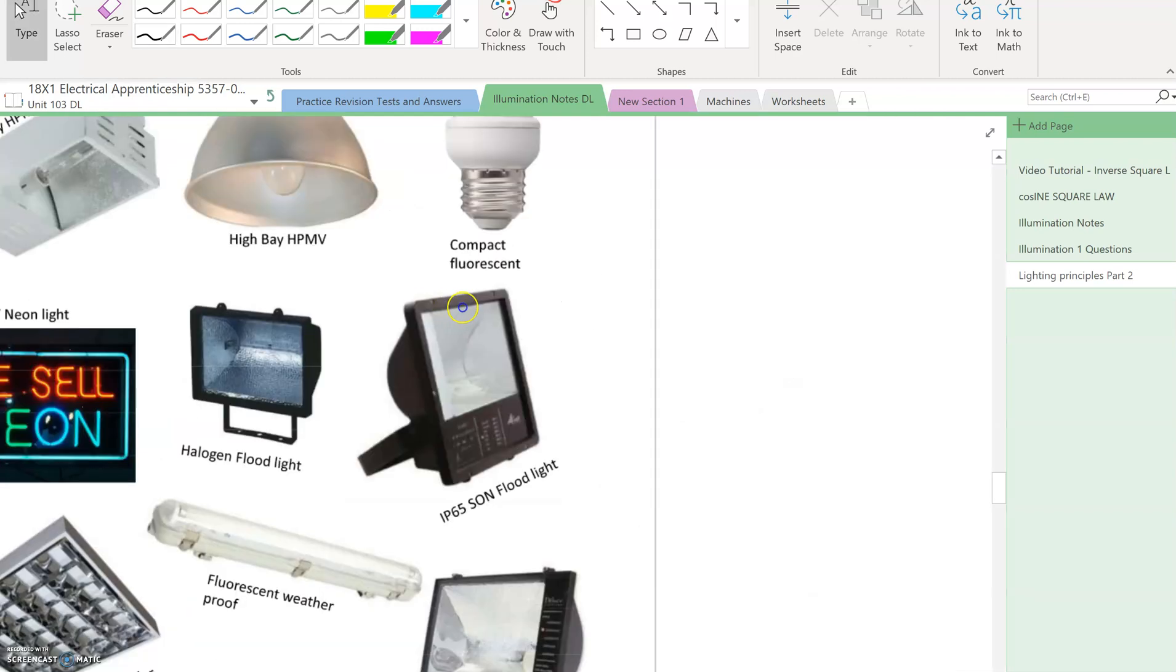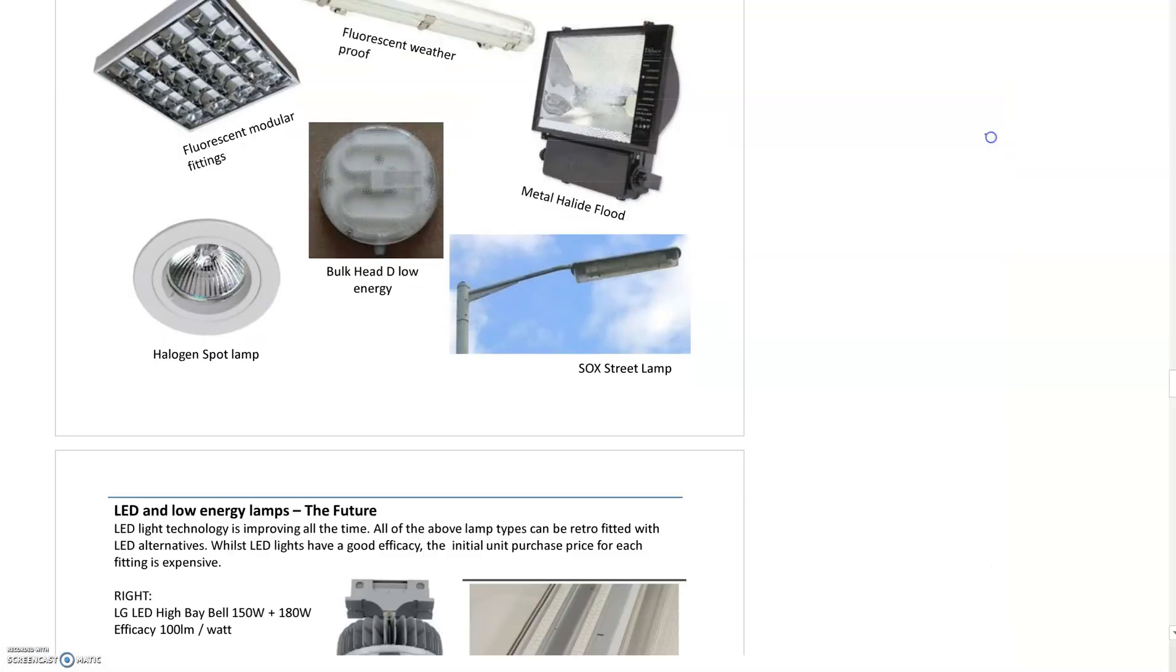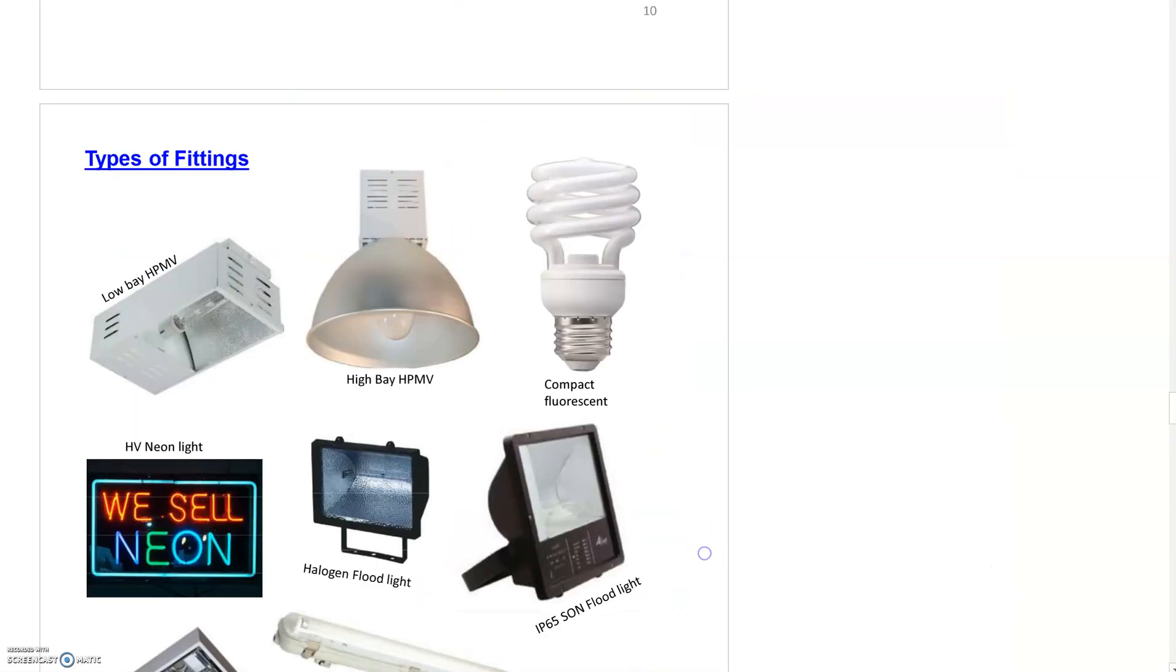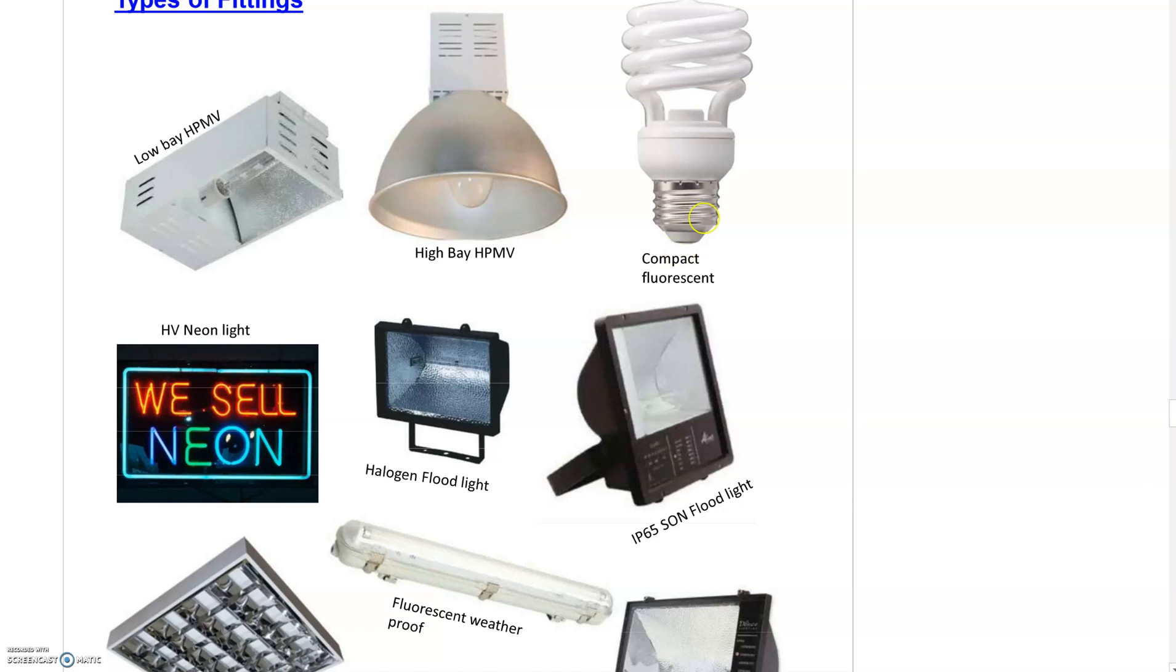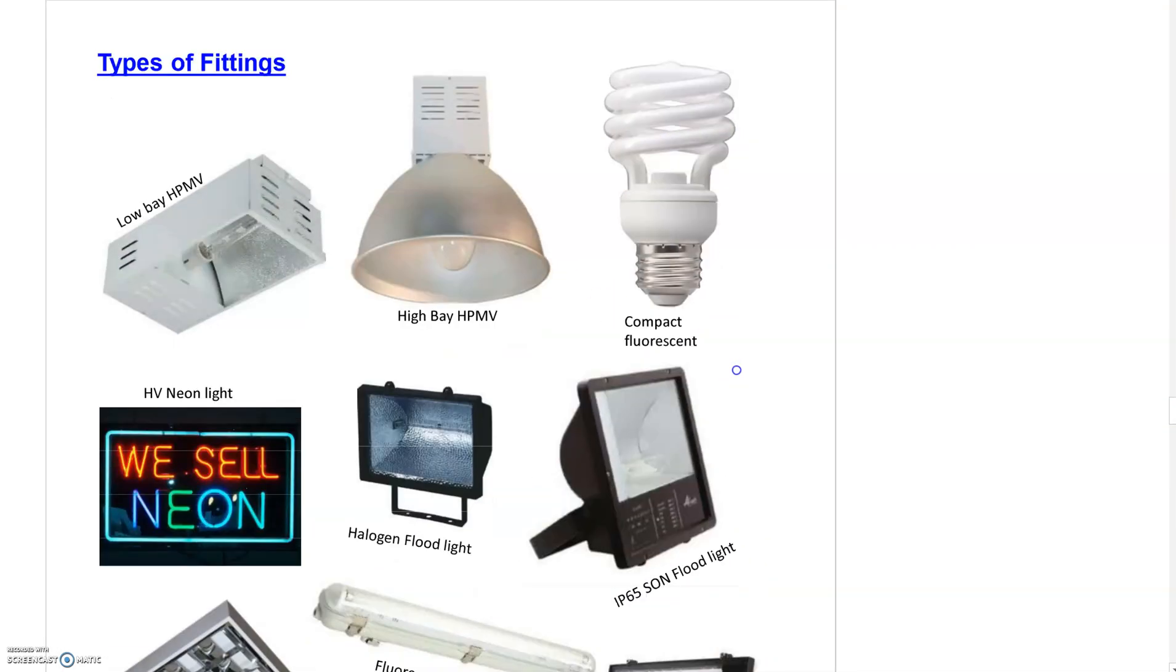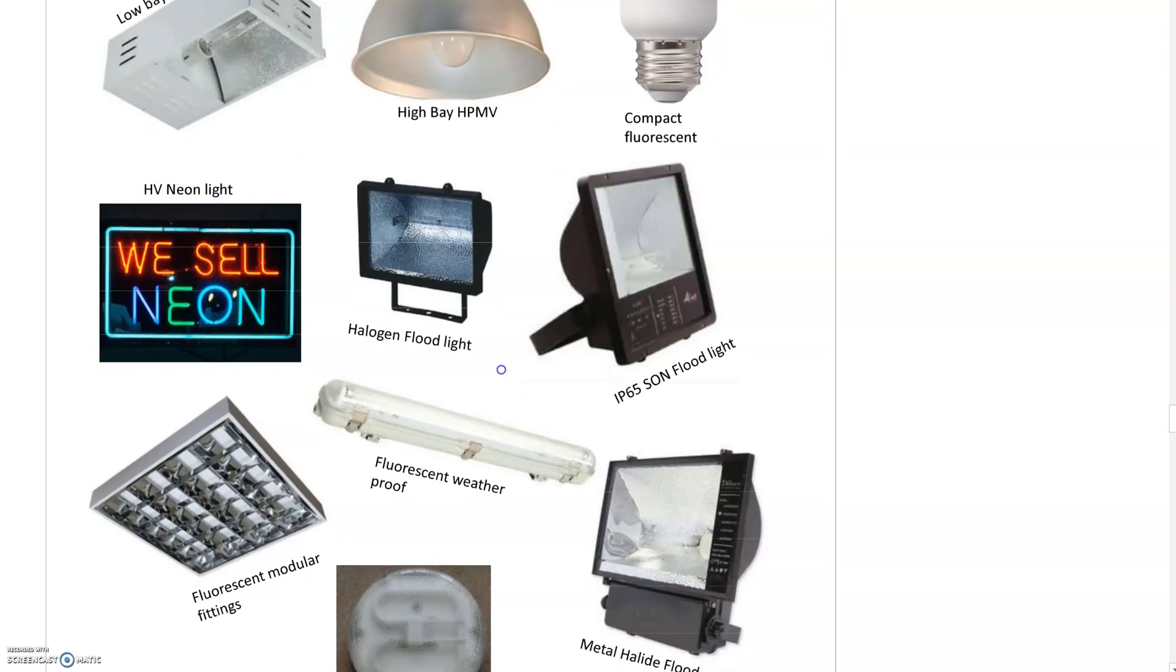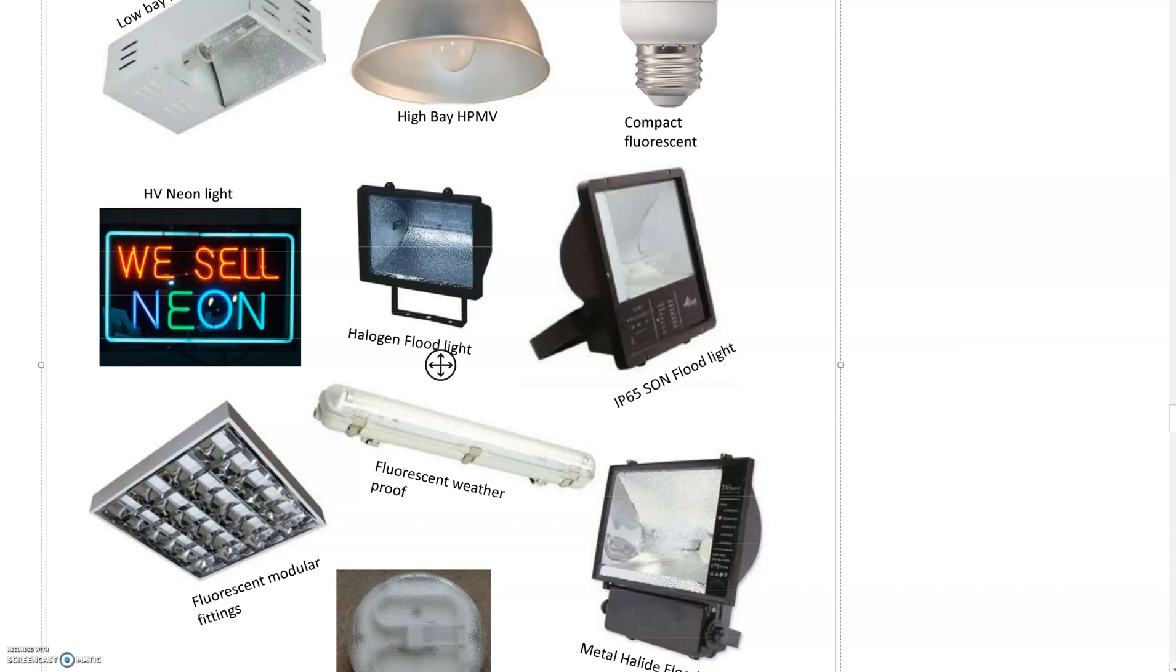Some examples of lights we may come across include low bays for industrial warehousing, high bays with high pressure mercury vapor, compact fluorescents which are disappearing and being replaced with LED, neon lighting which is high voltage requiring a fireman switch and runs at over a thousand volts, but being replaced by programmable LED.